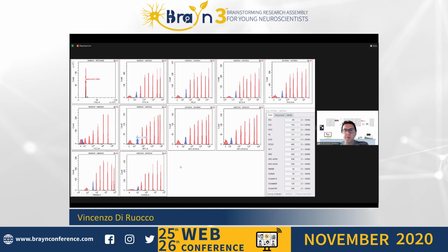So these are rainbow beads. These are commonly used to understand and compare instrument quality, and the separation that we can have among the first peaks across these beads gives you an idea about the sensitivity and the resolution. As you can see, there are clear separations, and this will enable researchers to really differentiate small differences between what is negative and what is really dimly positive.